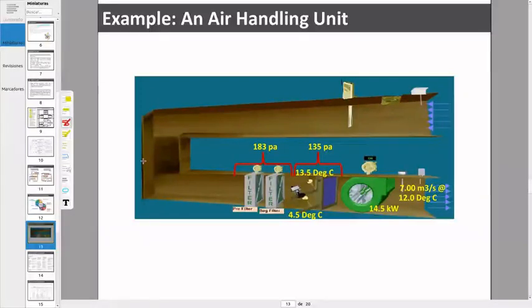Now what you see here is an extract from BMS in some cases, and we applied some pressure sensors, and we were able to measure the flow rate. We make sure that the supply temperature is acceptable. Now that can all be linked to the BMS and give us alarms so we make it more predictive.